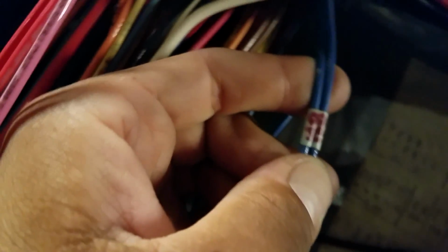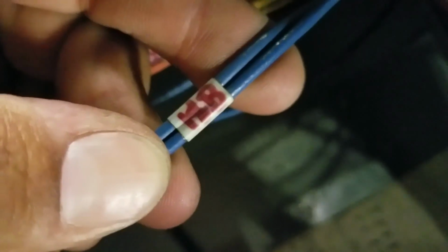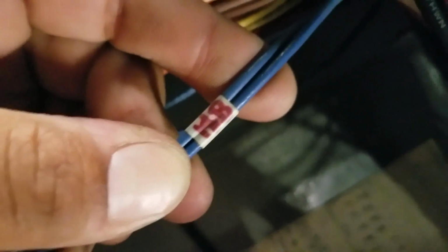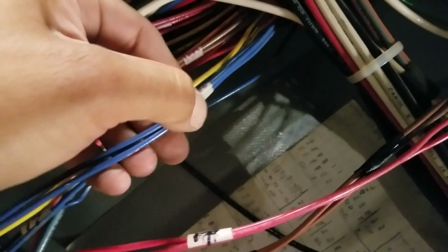So what I did was I pulled all the wires. That one I know it's controlling, and I pulled it all the way to right here. And right here, that says 18B as in Bravo. So I know 18B as in Bravo is controlling the solenoid. So that controls my defrost. So let's go back to the controller.